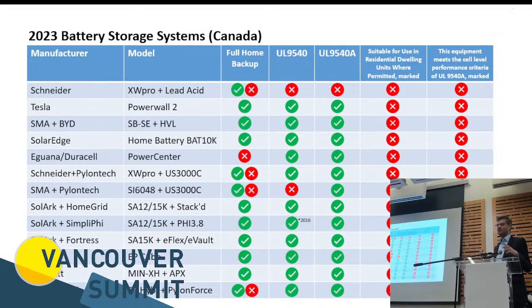And specifically challenging is if you have multiple vendors in your system. So you have the inverter from one manufacturer and the battery from another manufacturer, versus a complete system that comes from one manufacturer, because typically it's a sort of blame game. Who is doing the certification? Who is going to pay for the certification? Most manufacturers just push the responsibility to each other, and it takes a lot longer. With a fully integrated system like a Tesla or a CSI or Growatt or other brands, the same manufacturer provides the inverter, the cabinet, and the battery system, and they only have themselves to blame if they don't have the right certification. So that makes it a little bit easier.